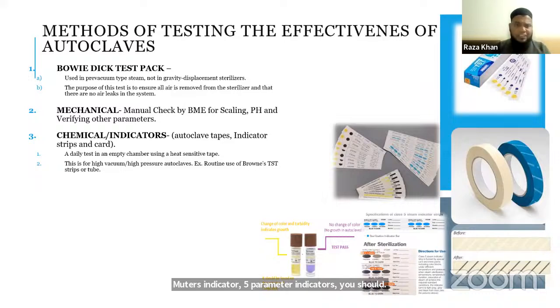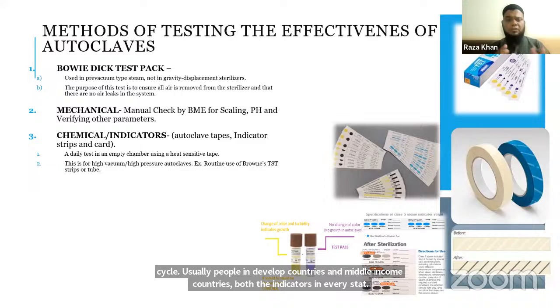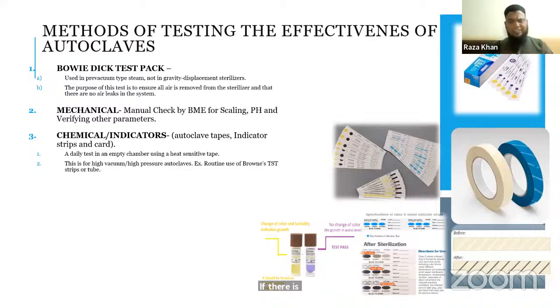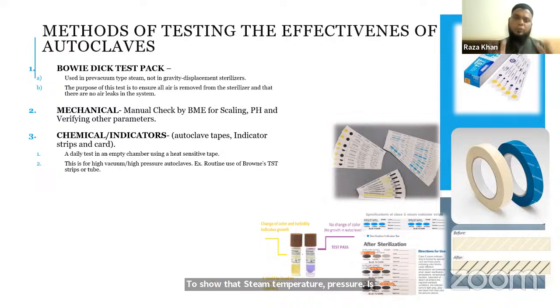These chemical indicators are usually used in every cycle. Usually, people in developed countries and middle income countries put the indicators in every pack. If there is a limitation, then people can skip, but it is recommended to put an indicator in every test and every pack to show that steam, temperature, and pressure are sufficiently provided to that load or that cycle.